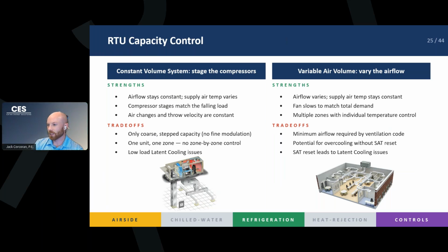Without overcooling, with this variable air volume system, you can have a little bit more of a complex control configuration where you reset the temperature similar to the constant volume system. If all of your zones are satisfied, you can have a supply air temperature reset, and then you're sending higher temperature air, maybe not as much in variable temperatures, because you still want to be able to maintain your zone minimum airflows. But you don't have to change the air temperature as much if you're also controlling the air volume.